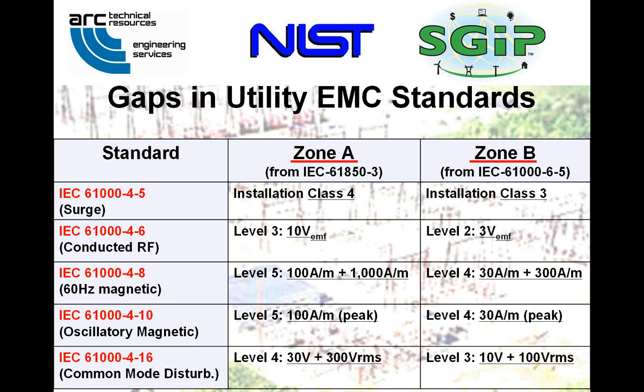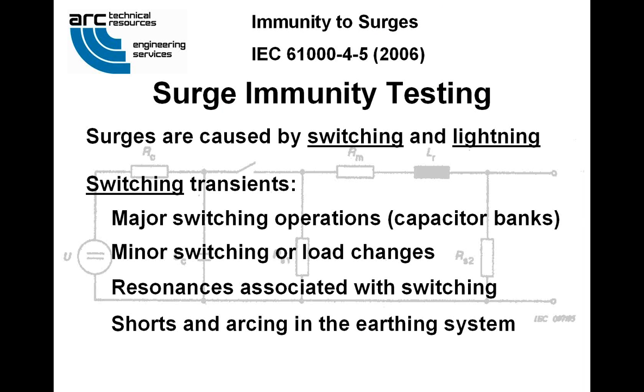IEC 61000-4-5 is surge immunity testing. Unidirectional overvoltages are caused by switching and lightning transients. Switching transients are associated with major power system switching like cap banks, minor switching operations near instrumentation or load changes out in distribution, resonant circuits used with switching devices like thyristors, or short circuit arcing faults in the earthing system of the installations. Lightning transients are associated with a direct lightning stroke to an external circuit, outdoors usually, an indirect lightning stroke that induces voltage and currents on conductors, or earthing currents from nearby direct strikes coupled into the earthing network.